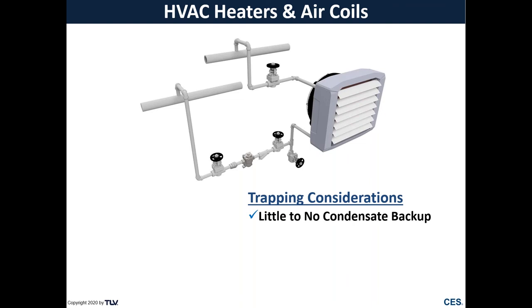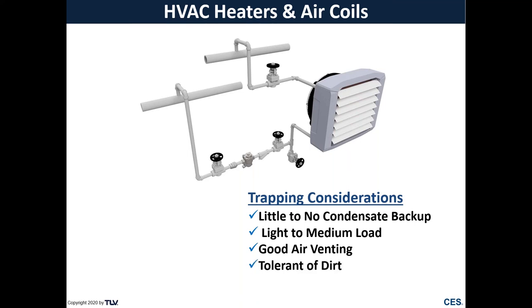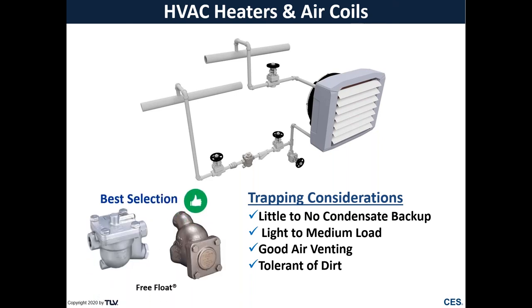So trapping considerations, we want something that has no condensate backup to prevent that freezing of those coils. And the load on these are typically going to be a light to medium load, maybe a few hundred pounds an hour, but definitely more than our typical drip or tracer application. We're going to want something with good air venting, as well as something that's tolerant of dirt. Now, one thing with these types of applications is they're often seasonally used, meaning that they're turned off once it's springtime and they're never turned on again until the beginning of heating season in fall. That gives the system plenty of time to build up dirt and scale and rust, which will then be flushed into the steam traps on startup. So we want to make sure that we can handle that. Best selection for this type of application is going to be a mechanical style trap, such as a free float.